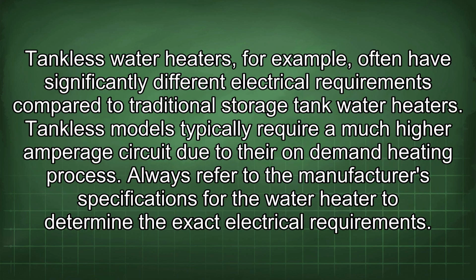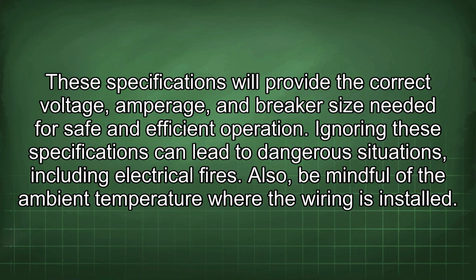Tankless water heaters, for example, often have significantly different electrical requirements compared to traditional storage tank water heaters. Tankless models typically require a much higher amperage circuit due to their on-demand heating process. Always refer to the manufacturer's specifications for the water heater to determine the exact electrical requirements. These specifications will provide the correct voltage, amperage, and breaker size needed for safe and efficient operation. Ignoring these specifications can lead to dangerous situations, including electrical fires.